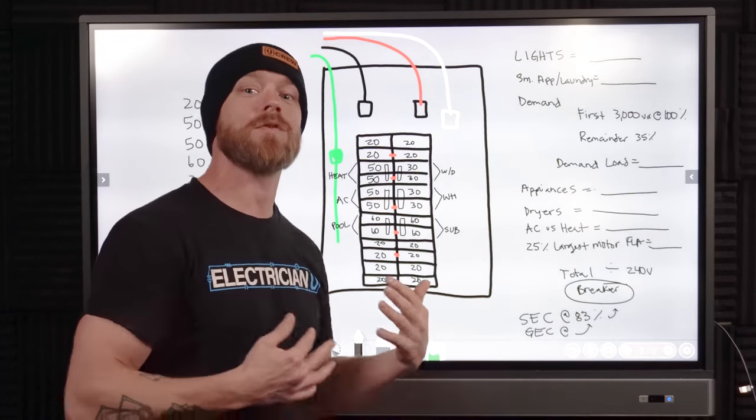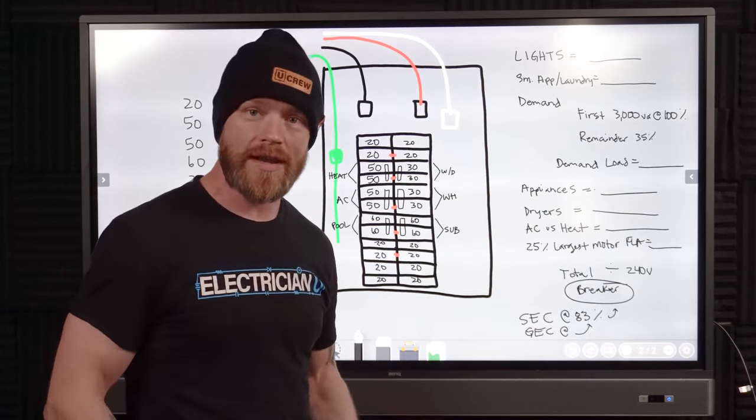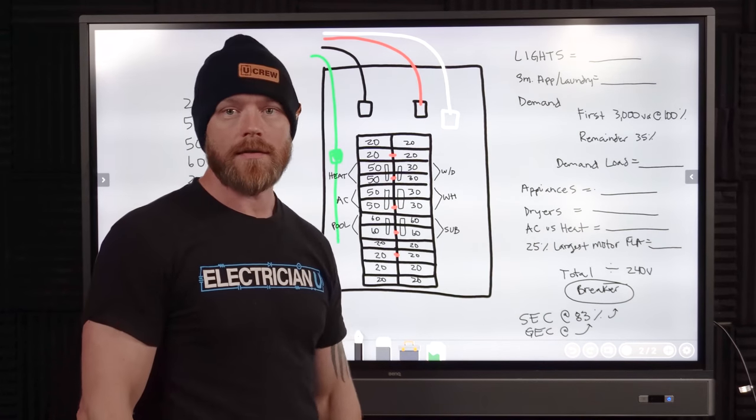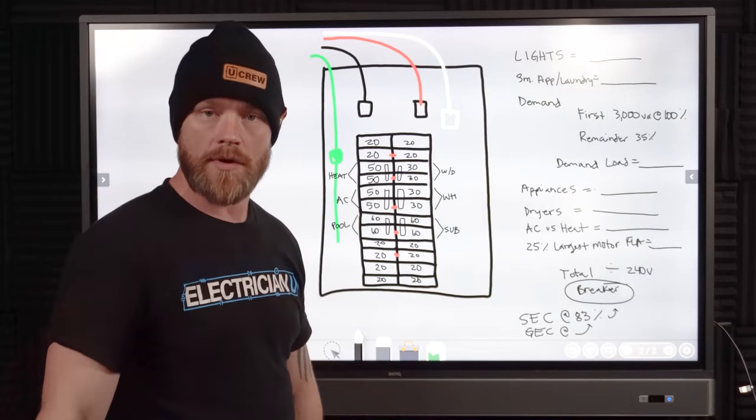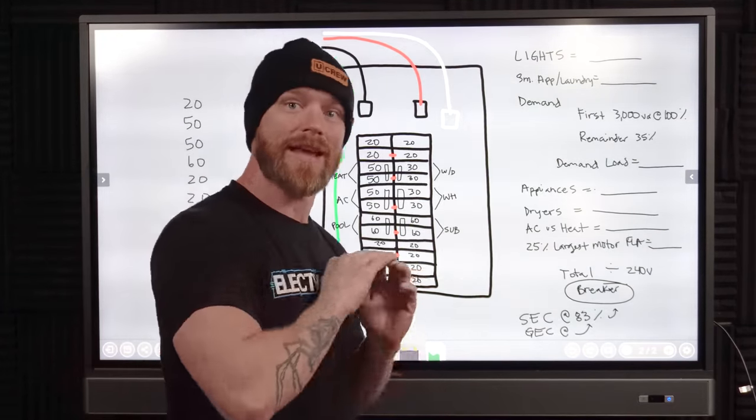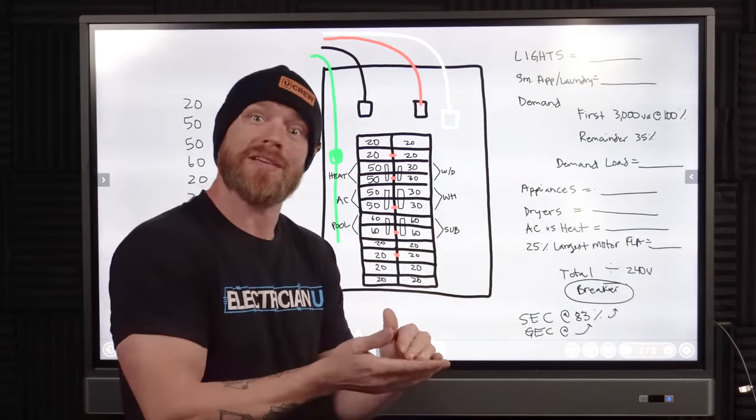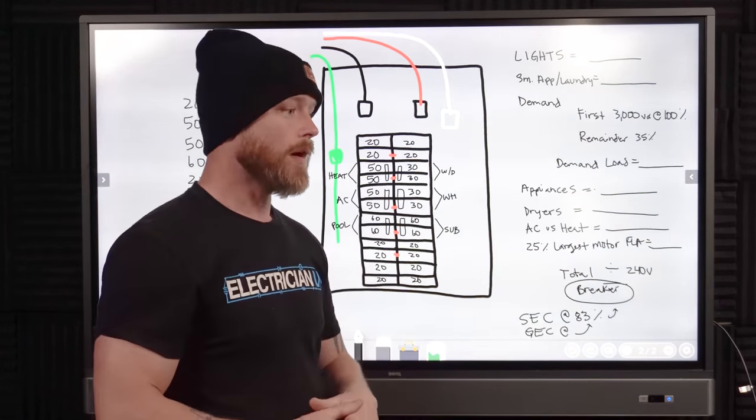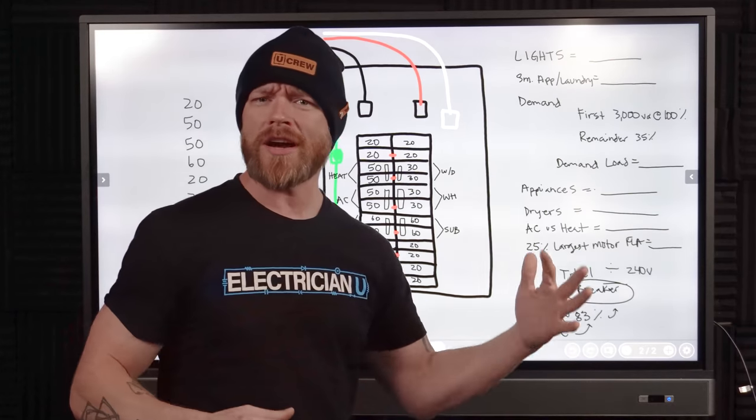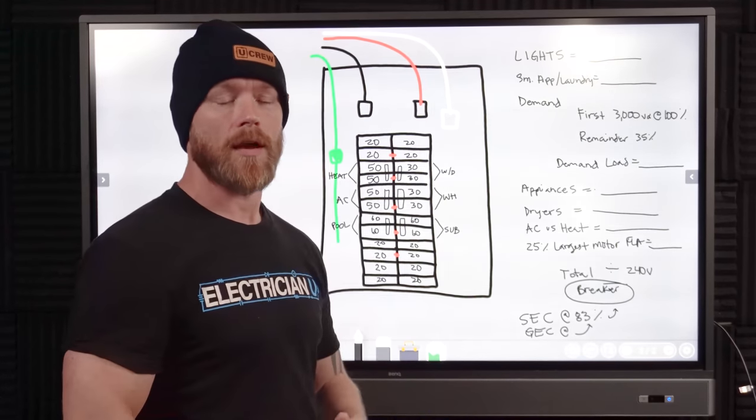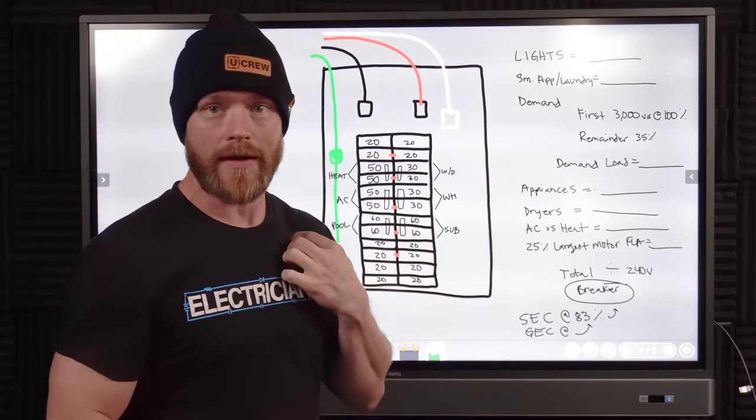Not every one of these things are going to be running at the same time. And so code allows us to de-rate things with the understanding that every once in a while we're going to be doing some drying clothes, every once in a while we're going to be cooking. There are some loads that are going to be running constantly at all times. So those ones we actually have to kind of bump up. We have to do 125% of that load if it's a continuous load.